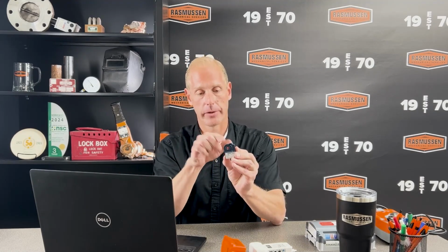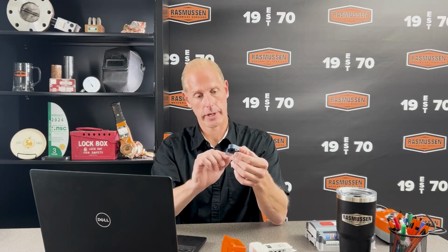The difference between analog would be a digital sensor like this one, which is either going to be on or off. This is what you call a current sensing relay. Power wire goes through the opening here. It reads the amperage going along that wire. And so when it reaches a certain level, which you can set, it will close a relay, which tells our controller that the piece of equipment that we're monitoring is actually running or not. If we send a signal from our output to run a fan, this is what's going to tell us if that fan is or is not running.